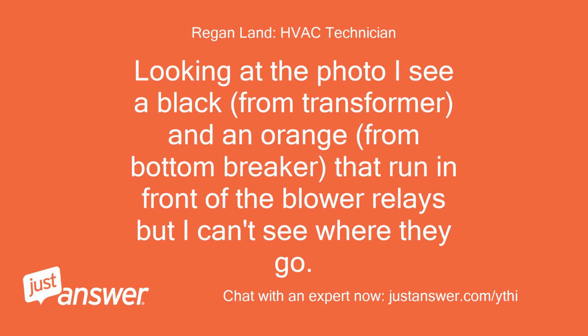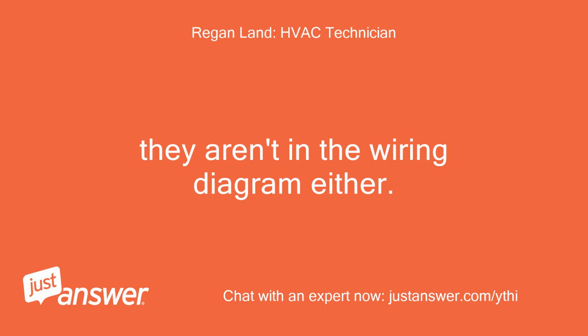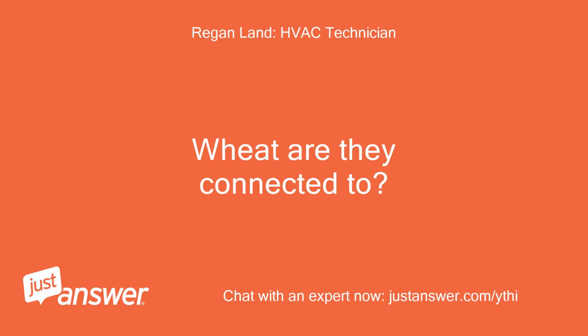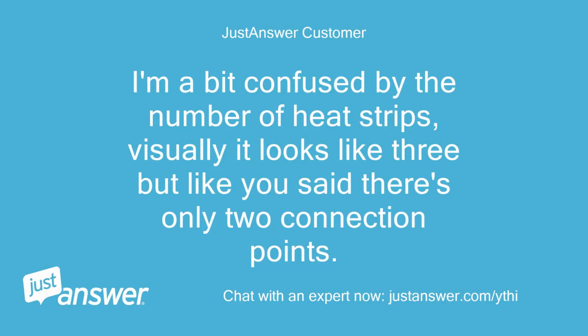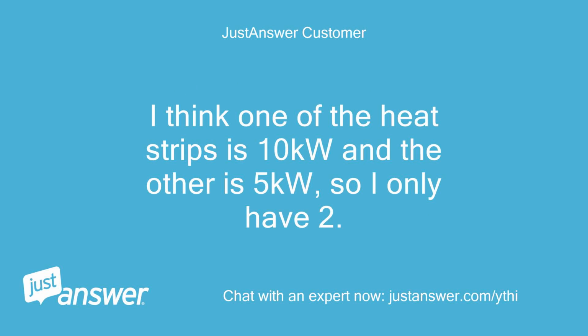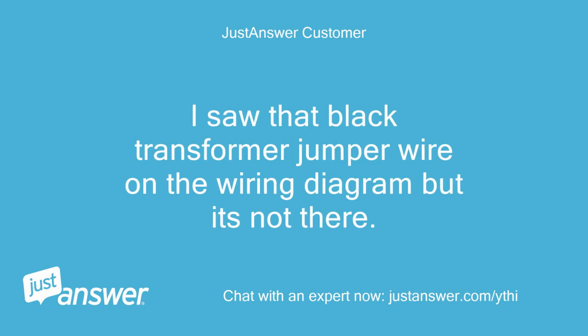Looking at the photo I see a black wire, from the transformer, and an orange wire, from the bottom breaker, that run in front of the blower relays but I can't see where they go. They aren't in the wiring diagram either. What are they connected to? I'm a bit confused by the number of heat strips. Visually it looks like 3, but like you said there's only 2 connection points. I think one of the heat strips is 10 kilowatts and the other is 5 kilowatts, so I only have 2. I saw that black transformer jumper wire on the wiring diagram, but it's not there.